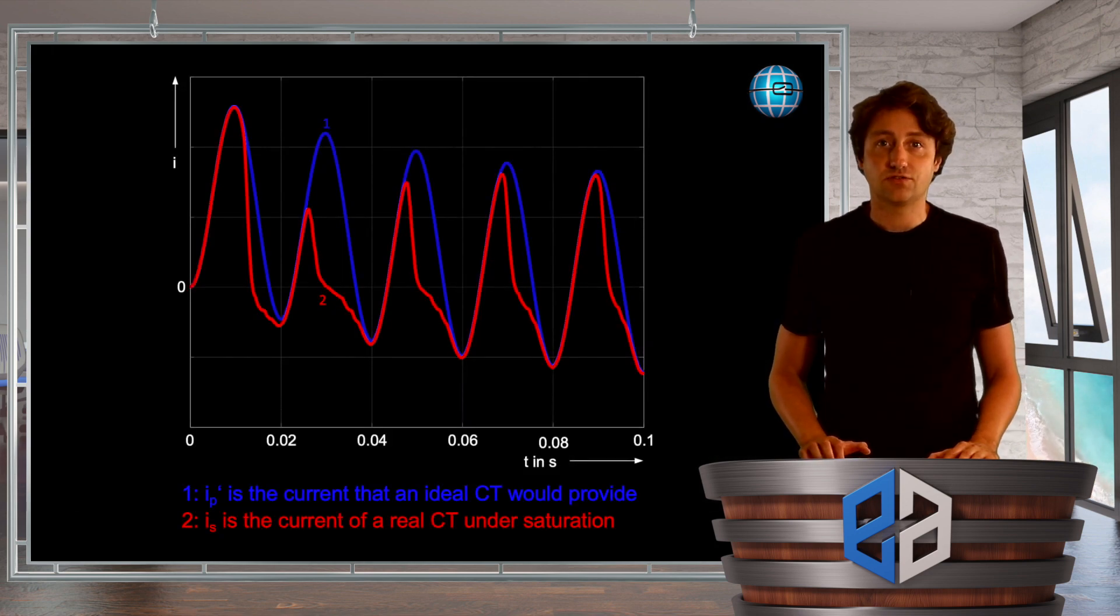During the lifetime of a current transformer, many faults have to be cleared in the system and each of the faults may add some remnant flux to the core due to the DC component of the fault. And likewise, DC measurements performed on the current transformers may add some remnants as well.